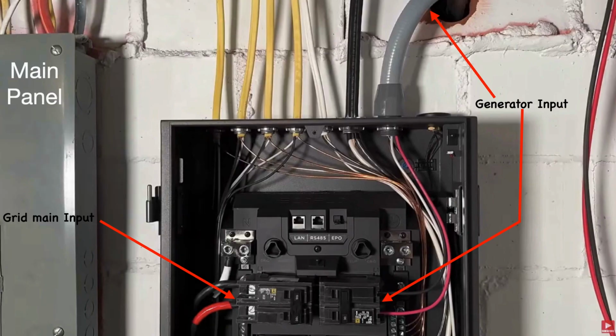We have already seen, in a previous video, a subpanel could be the means by which standby power is supplied to a home. This slide shows an actual installation of a smart home panel 2, that has both the generator input, as well as connection to the main grid panel. You can see the circuits that need to be secure entering the panel at the top and are tied to the individual breakers inside this panel. Installers have drilled holes to connect the NMD cables for 1 to 12 load circuits.